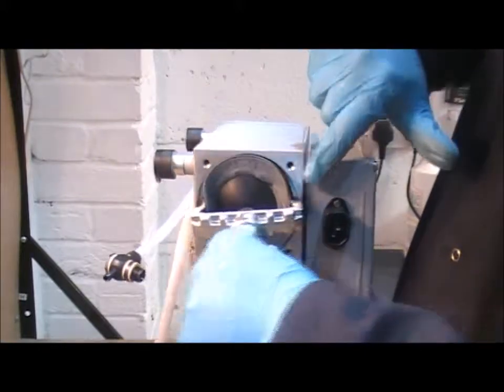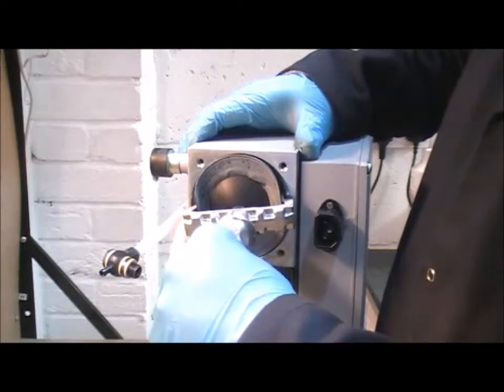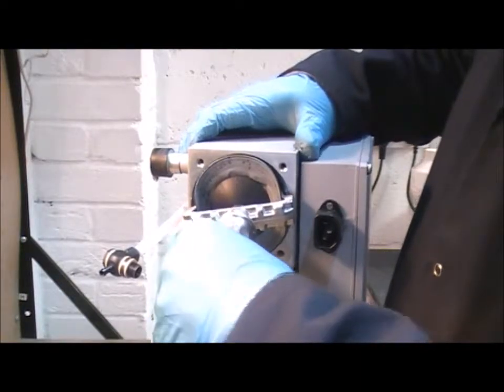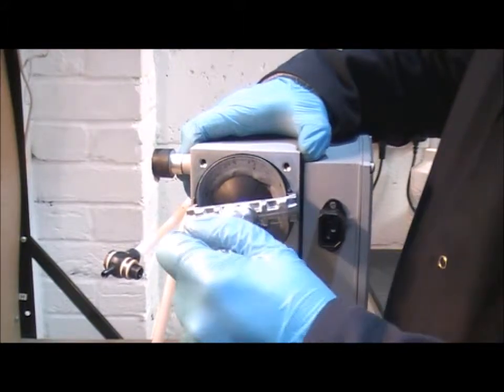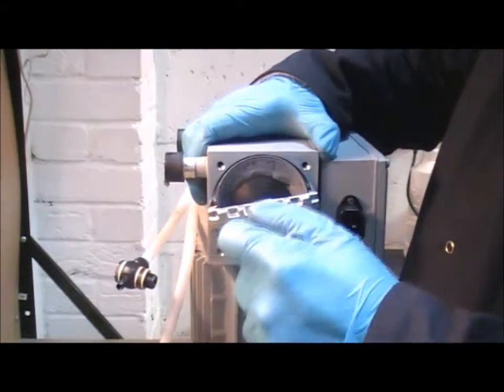Then you can look in from the side here. You'll see it a bit more clearly in a moment. I can see that there are flats on the plate behind the diaphragm. I've just got to rotate the tool until it catches those two flats. Now it's nice and secure, I can go ahead and unscrew the whole assembly using that tool.